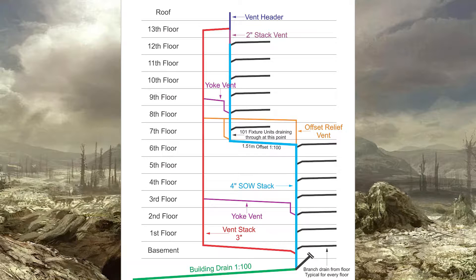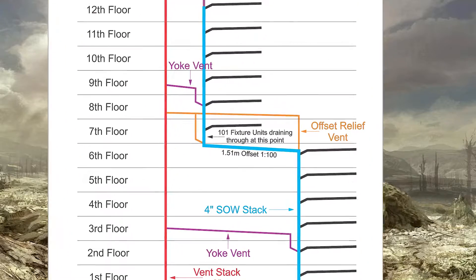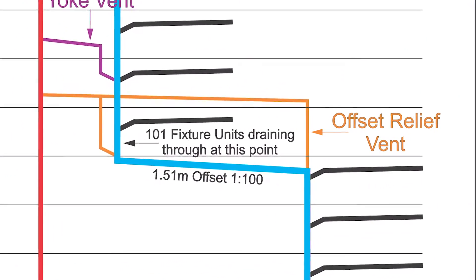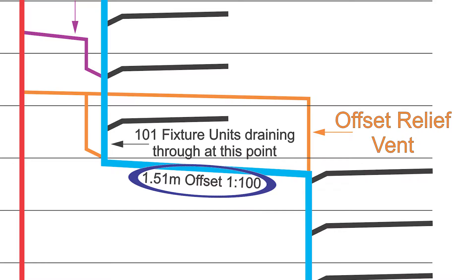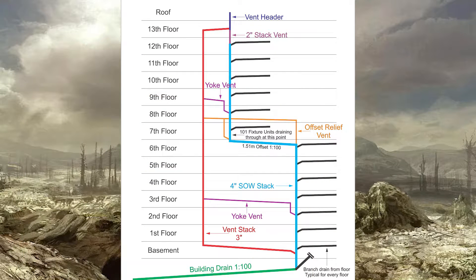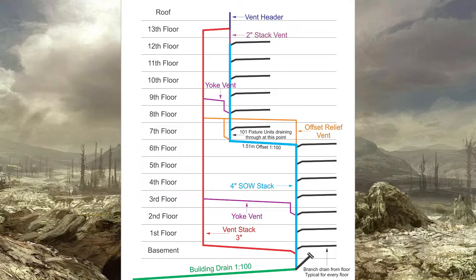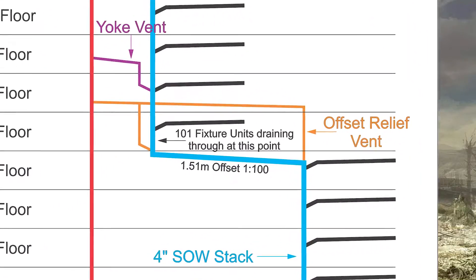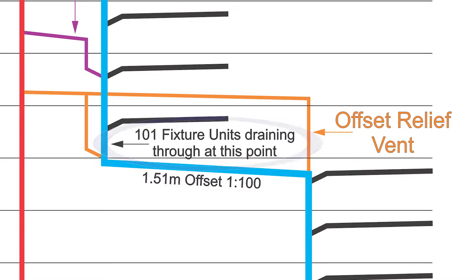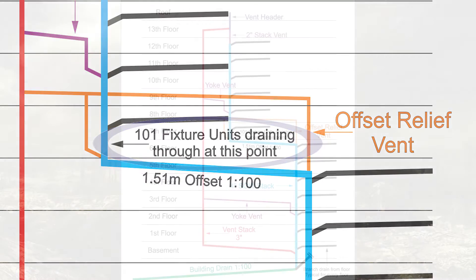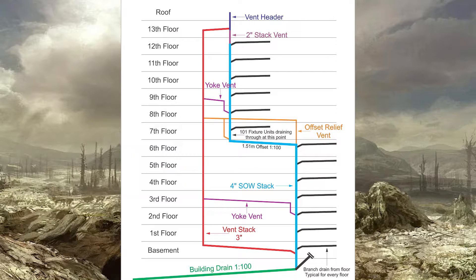First of all, when do you need it? Your offset needs to be more than 1.5 meters — my offset is at 1.51 meters. Next, I need to be receiving discharge from more than two stories above the offset — I've got about six stories discharging into the offset. And I need to have more than 100 fixture units draining into that offset — I have 101. I have to meet all three of those requirements before I need an offset relief vent, and I have, so now I need one.